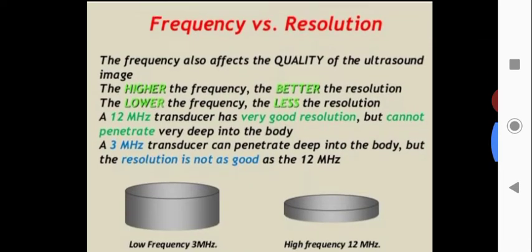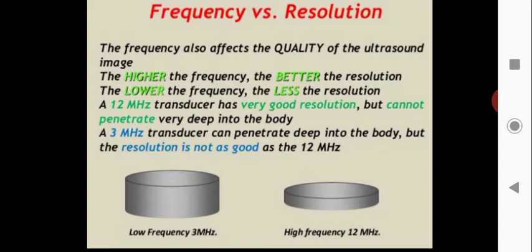The thickness of the crystal determines the frequency of the scan head output. If the thickness of the crystal is small, it will generate a high frequency. If the thickness of the crystal is large, it will generate a low frequency. Frequency also affects the quality of the ultrasound image.